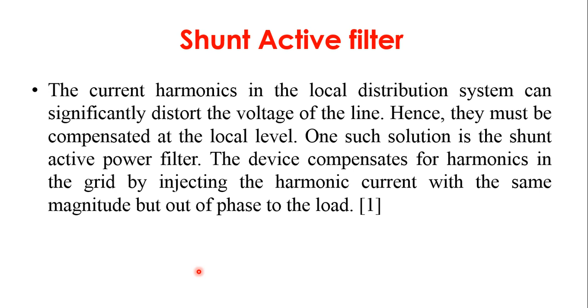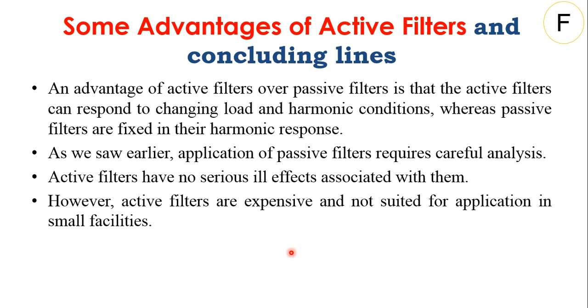A particular advantage of active filters is that they can respond to changes in load harmonic condition, whereas passive filters are fixed for a particular harmonic response. The application of passive filters requires careful analysis, and active filters have no serious ill effects associated with them. The main problem is that active filters are expensive and not suitable for small applications in terms of power.